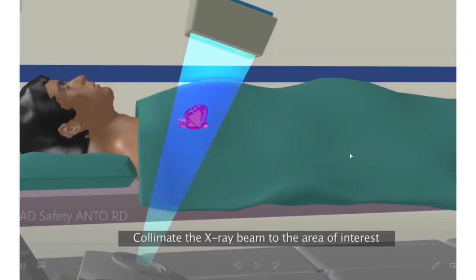Collimate the X-ray beam to the area of interest. So you have to understand, in order to reduce the dose and also to increase image quality, always collimate the X-ray beam to the area of interest. So don't open it widely, that is not required.